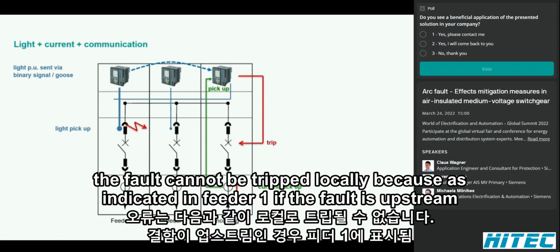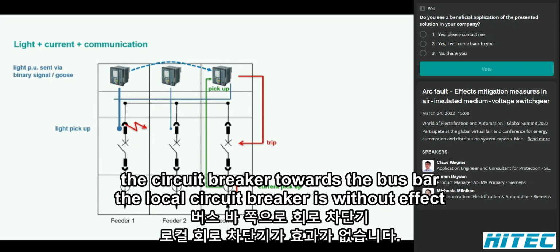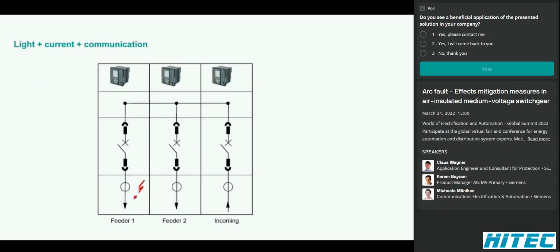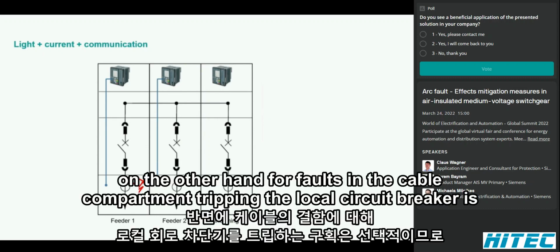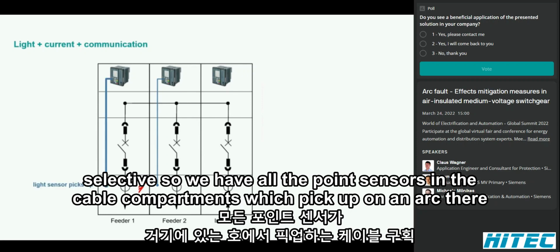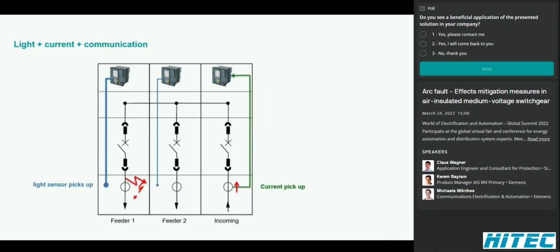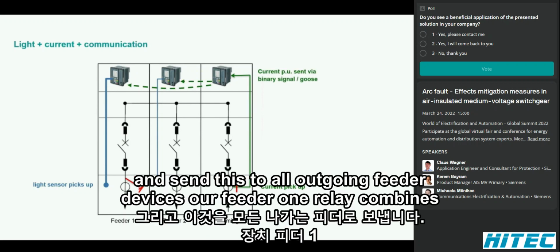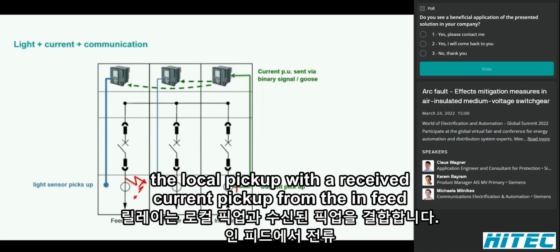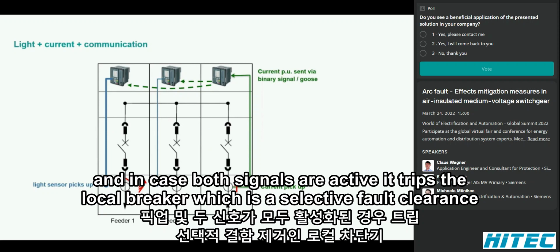The fault cannot be tripped locally because, as indicated in feeder 1, if the fault is upstream the circuit breaker towards the busbar, the local circuit breaker is without effect. On the other hand, for faults in the cable compartment, tripping the local circuit breaker is selective. So we have also point sensors in the cable compartments which pick up on an arc there. The incoming feeder protection sees a current pickup and sends this to all outgoing feeder devices. Our feeder 1 relay combines the local pickup with the received current pickup from the in-feed, and in case both signals are active, it trips the local breaker, which is a selective fault clearance.